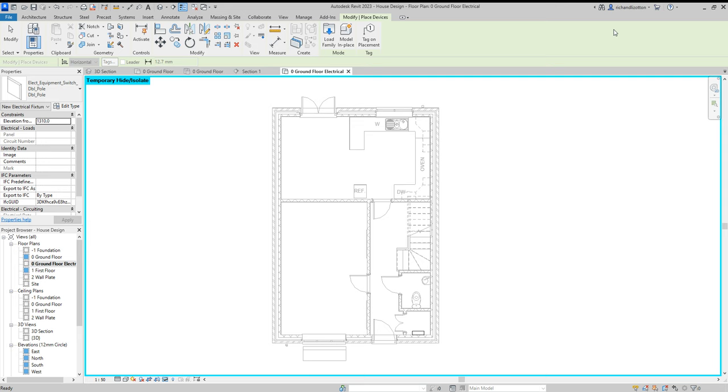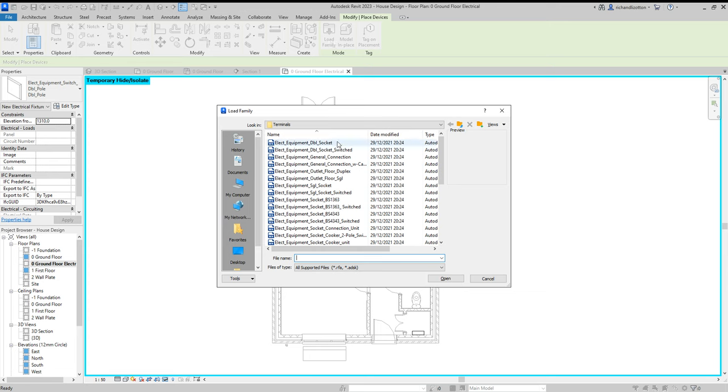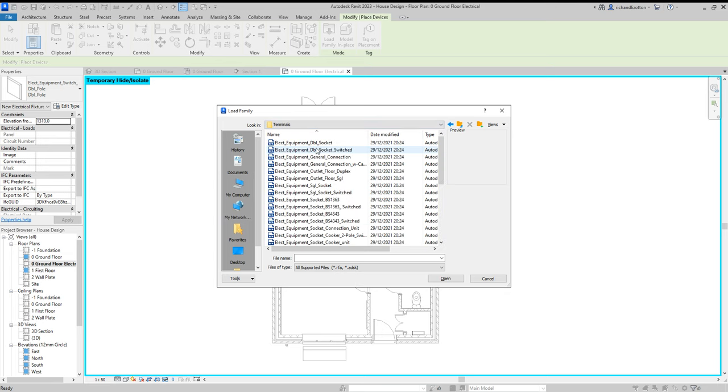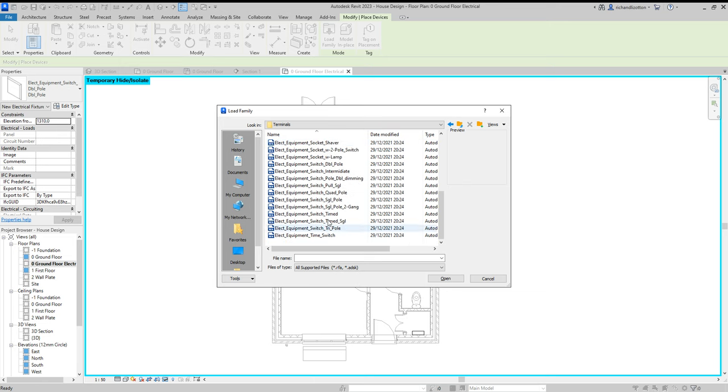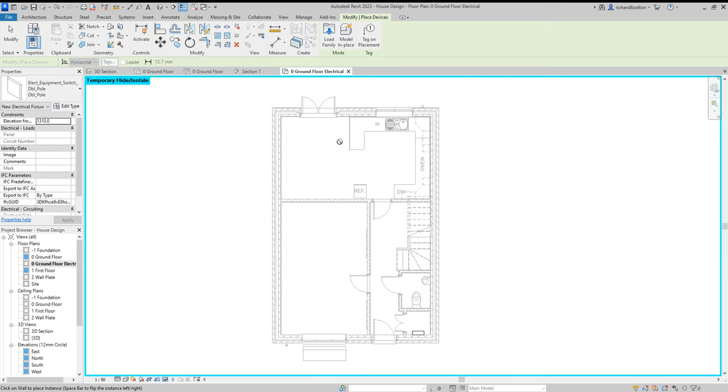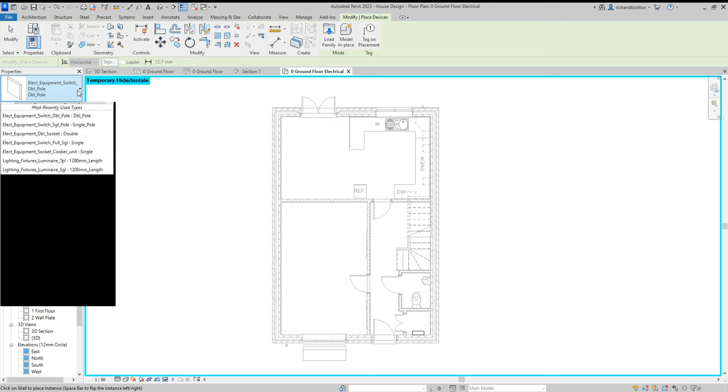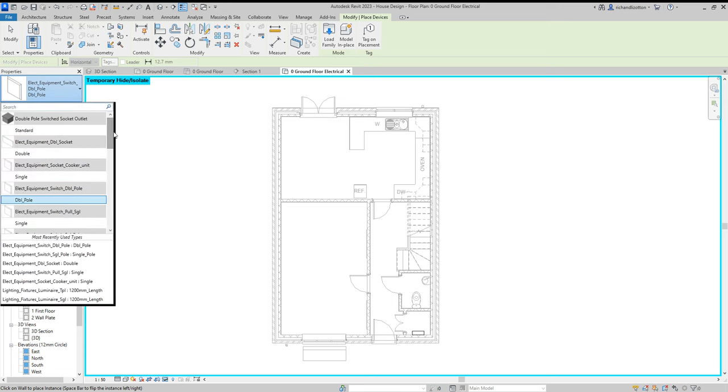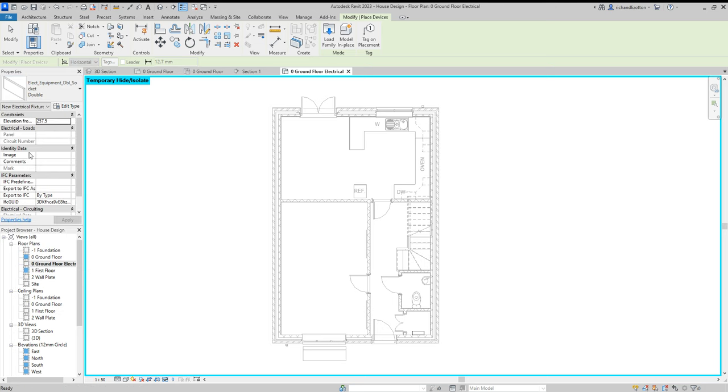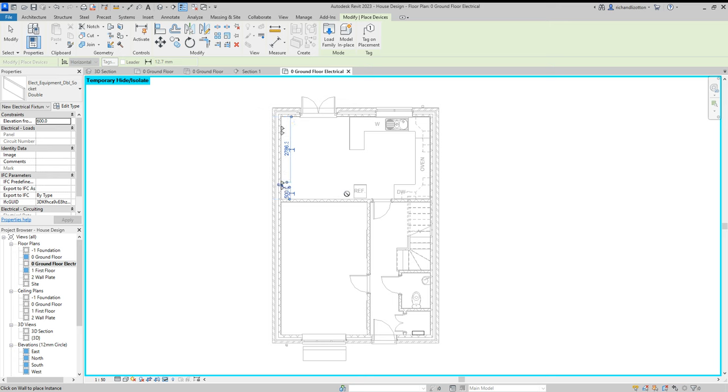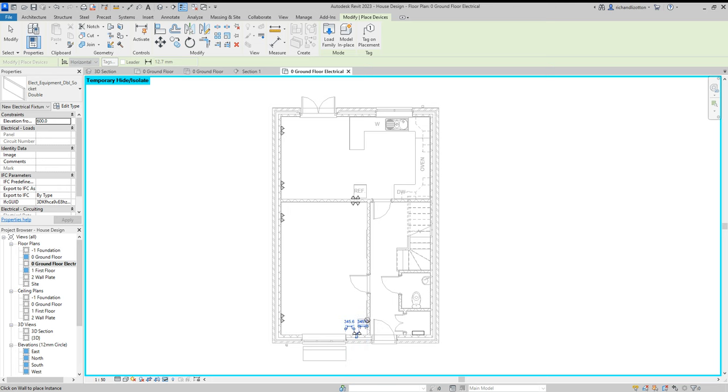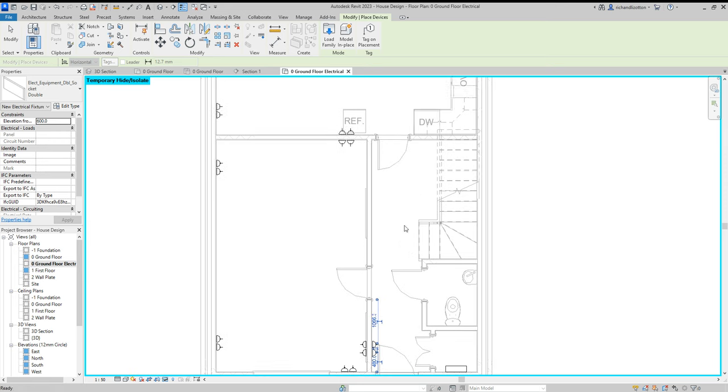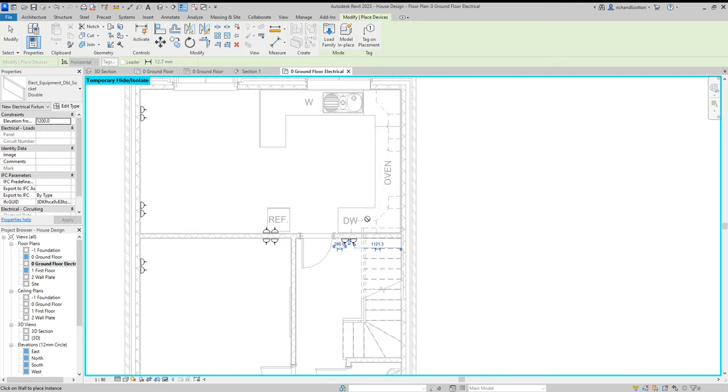Next, devices. And again, load family. So this time you want to go into the terminals folder rather than distribution. And pick whichever sockets and switches you want and just load them in. I've already loaded quite a few in, so I'm just going to use ones I already have. And then we should have them in here. So we've got double sockets by there. Let's put some of those. Elevation from the floor. Well, I don't really want it at 257 off the floor. I'm going to make them 600 off the floor, and just drop them in as I go around.